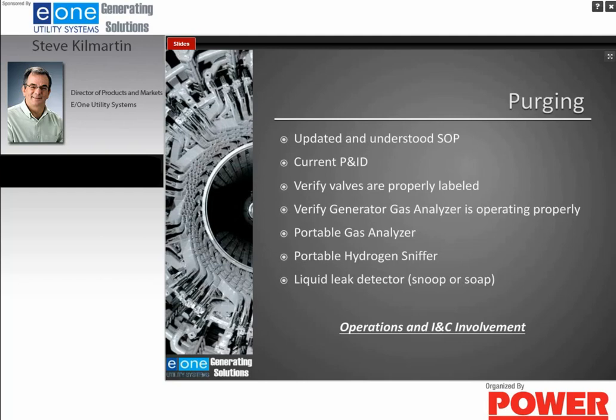Along with verifying that your P&ID is current, you need to verify that all the valves are labeled properly and that these labels are noted in the standard operating procedure and in the P&ID. Over the years, many of these valves will lose their labels or they become unreadable, so you need to make sure that the valves are properly labeled. You need to verify that your gas analyzer is operating properly and that it's calibrated. I would recommend also that you have a portable analyzer to support the readings you're getting out of your permanently installed analyzer, redundancy, if you will.